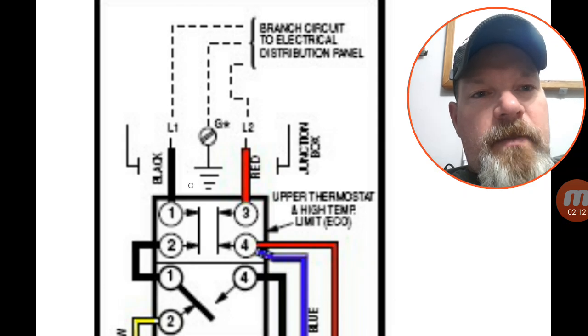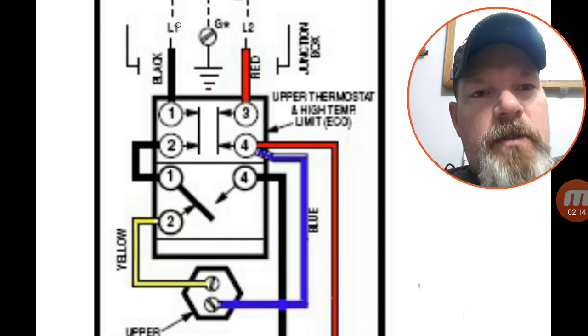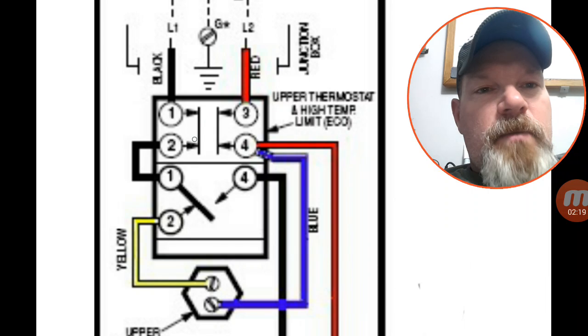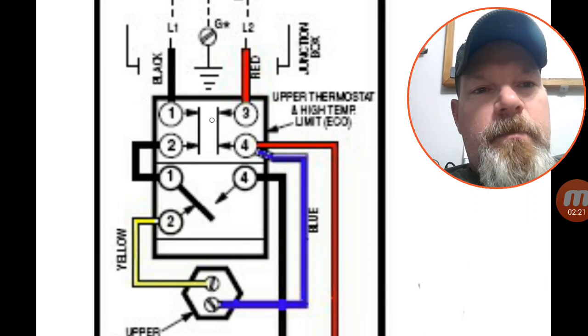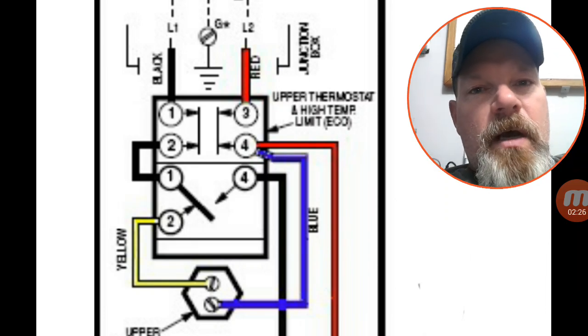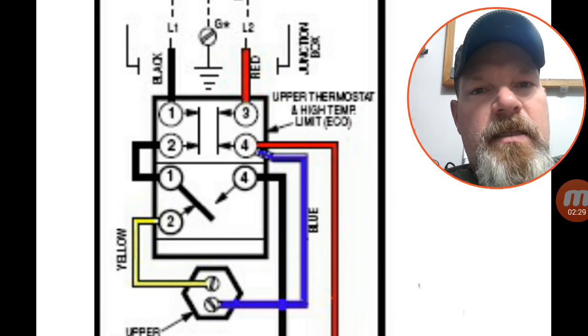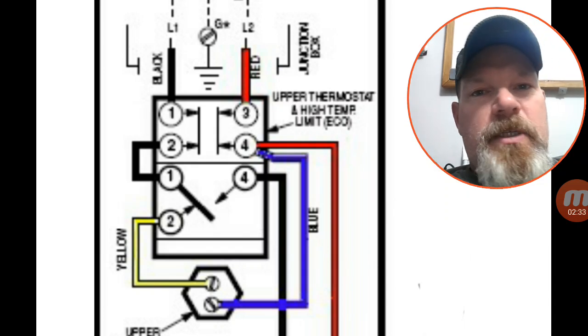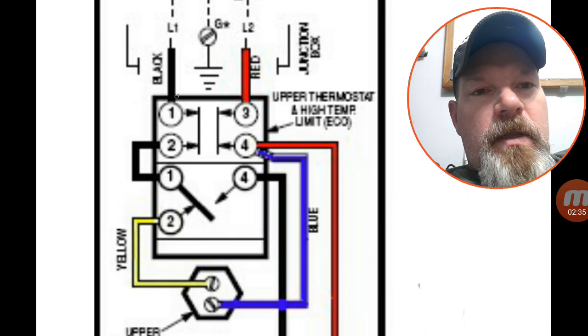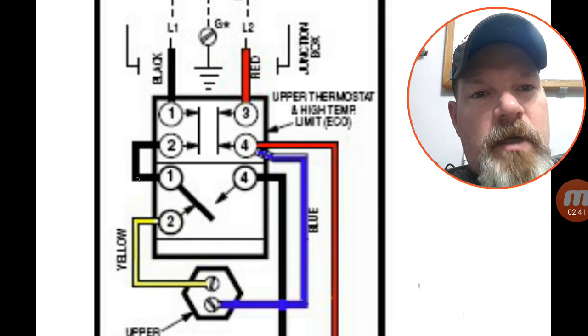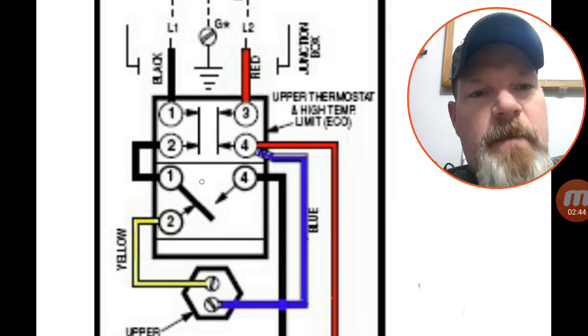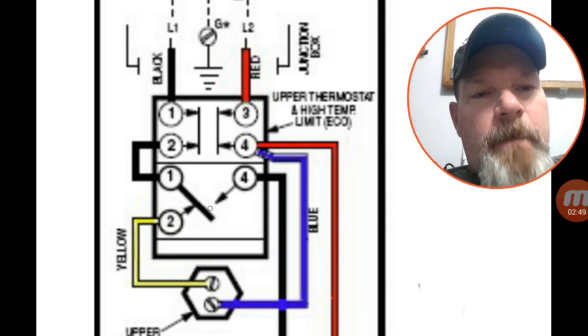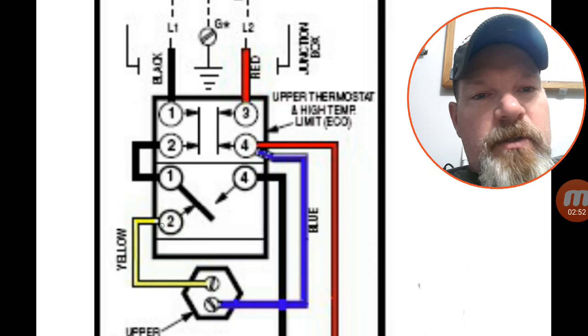Coming in on the L1 terminal goes to number one. Now this is going through one side of a limit switch, and there's typically that red button right here. What that is, there's a bi-metal plate on the back of the thermostat that's sensing the tank temperature, and if it gets too hot, boom, it just trips off. So that's what that's for. But when it's closed, the switch is sending power through and it goes down into number two, comes out and goes back into number one, which is the com leg of a single pole double throw switch.